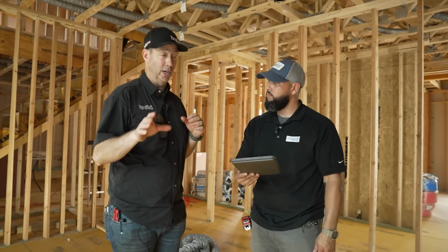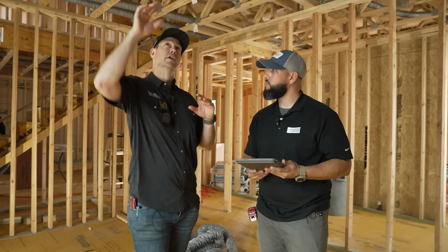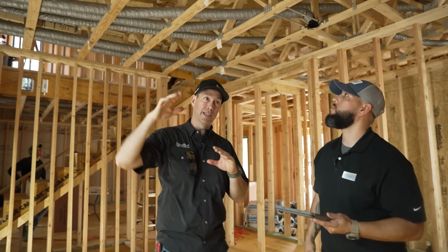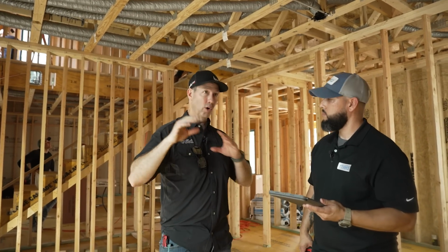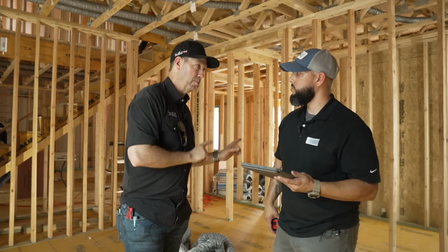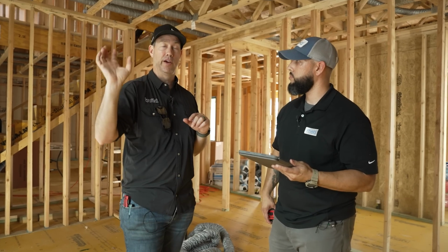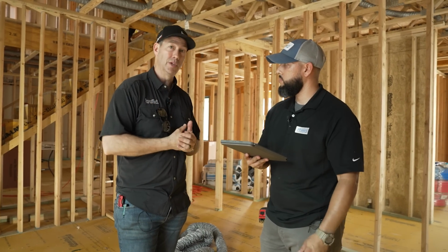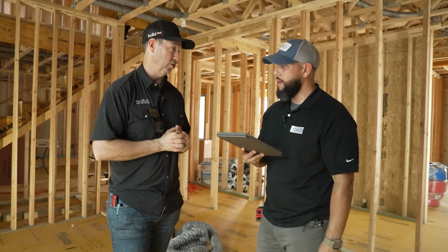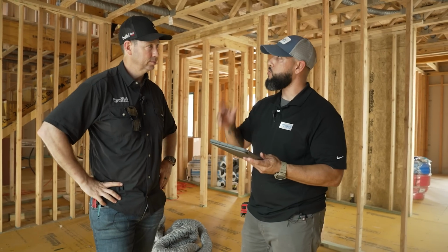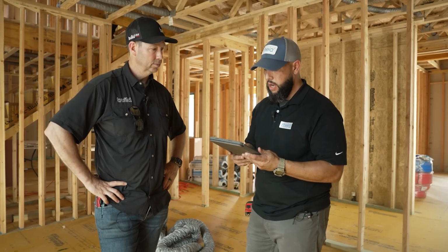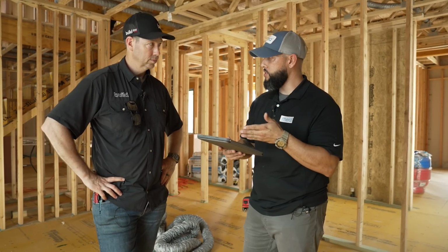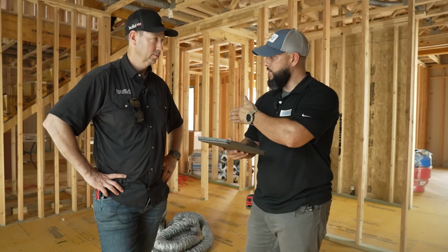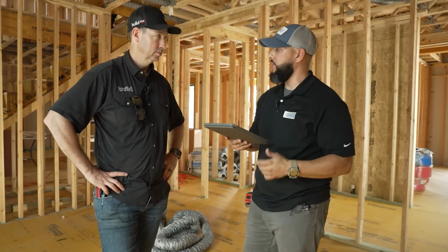But I think what's interesting, and we'll have to capture this later, is that each one of these outlets has a damper that's movable. We're gonna set it for a 2, but when we come to commission the job, we're gonna put a flow hood on there. And if it needs more CFM to meet that, we could actually change that damper position. Absolutely. Right? So through the Rheia Verify process, we'll come in and measure that airflow, as you mentioned. When we measure that airflow, we could compare it to the target, and then we'll enter the measured, and it gives us our delta, and we'll know where to place that damper position.